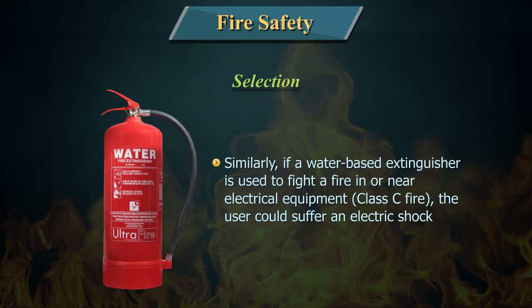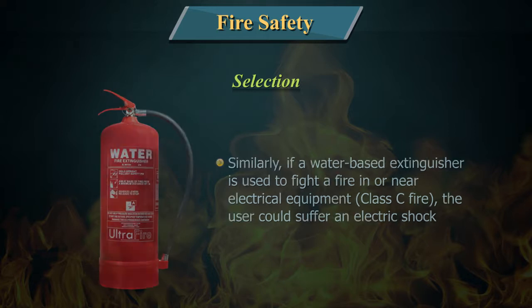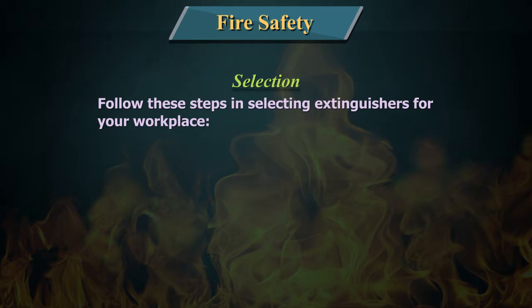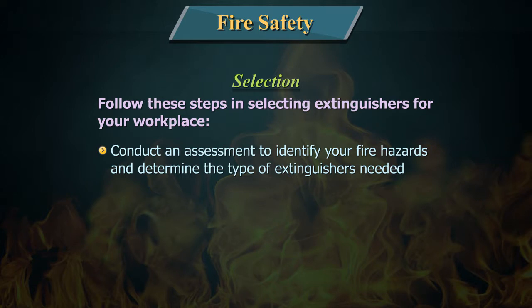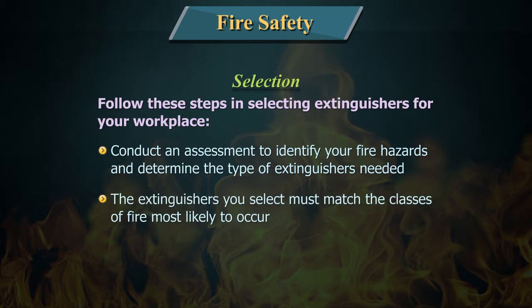Similarly, if a water-based extinguisher is used to fight a fire in or near electrical equipment (Class C fire), the user could suffer an electric shock. Follow these steps in selecting extinguishers for your workplace: 1. Conduct an assessment to identify your fire hazards and determine the type of extinguishers needed. 2. The extinguishers you select must match the classes of fire most likely to occur.